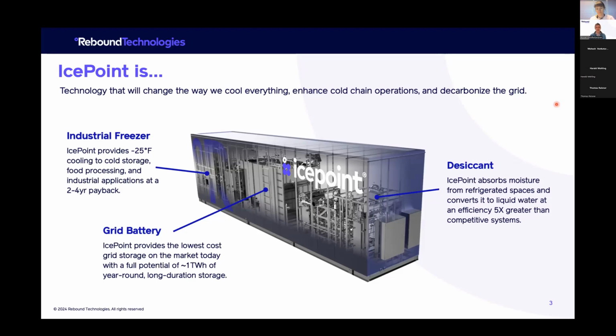The remaining 10 to 20% is the ability to arbitrage time-of-use rates to avoid demand charges. That conversation is much more about the additional cost of adding more storage. The system basically comes with 3 hours of storage for free, which is what we need to provide these two initial value streams. The grid battery part rides along at only the cost of adding more storage. So if we want to add 6 hours of storage to arbitrage time-of-use rates, that comes at a very low cost, because we only have to make our fiberglass insulated tank a little bit bigger, allowing a 1 to 2 year payback on that storage component.